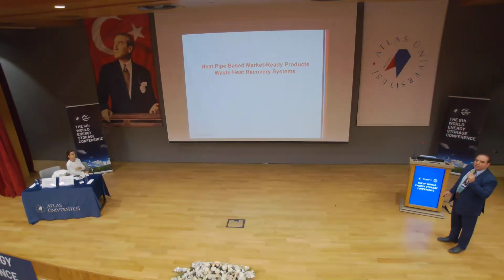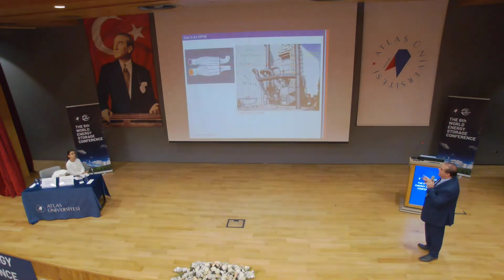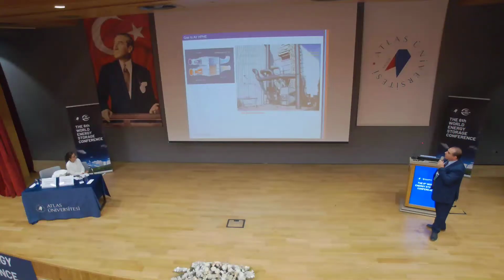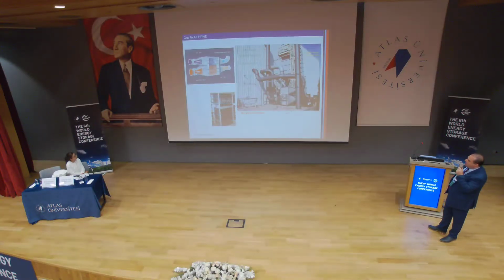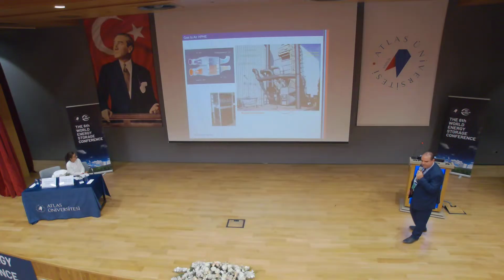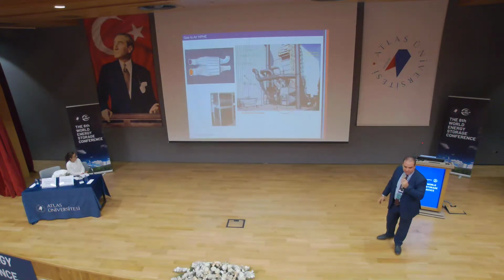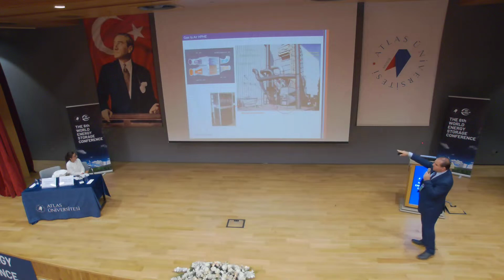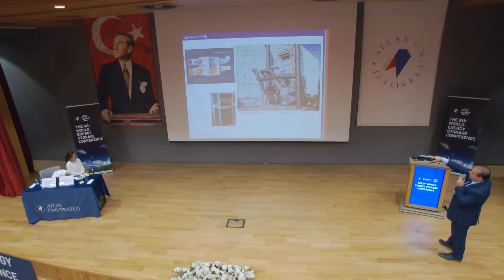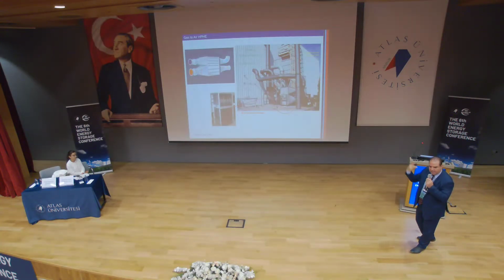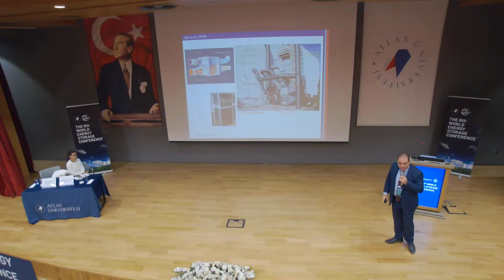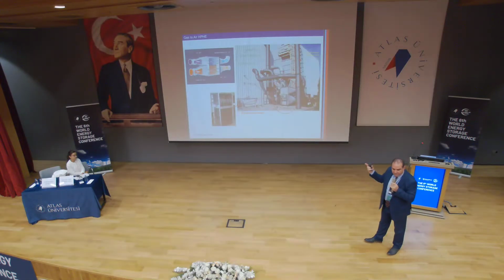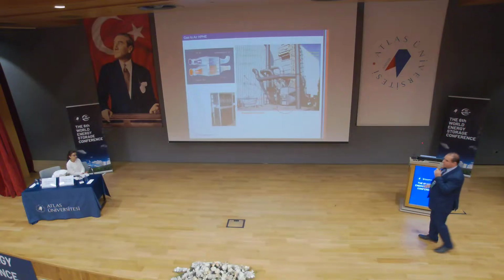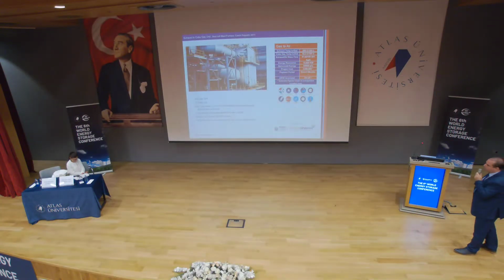So what about the systems in the market now that came from this process? Here's a scenario in Canada. You can see simply a box. If you take the box out, you can see a heat pipe system, many heat pipes staggered in a certain configuration based on the thermal design, with a separation plate in the middle. Exhaust flows at the bottom, heat is absorbed and provided to the combustion air, which takes that heat and heats the combustion air. By doing so, you don't need as much fuel as you would if the combustion air was cold. This is a very good example of a system that is still operational.